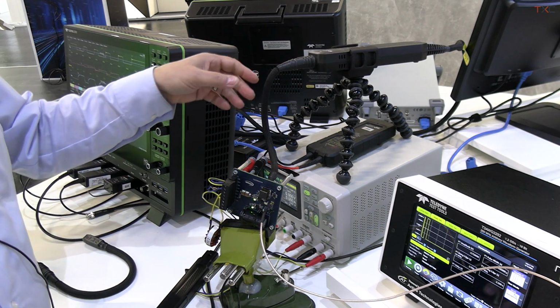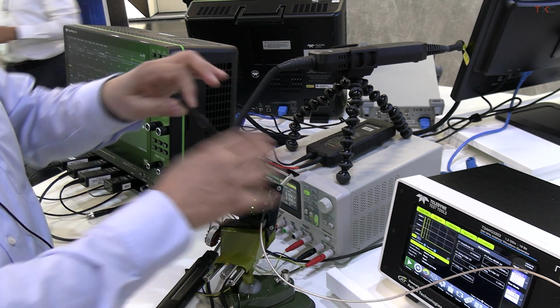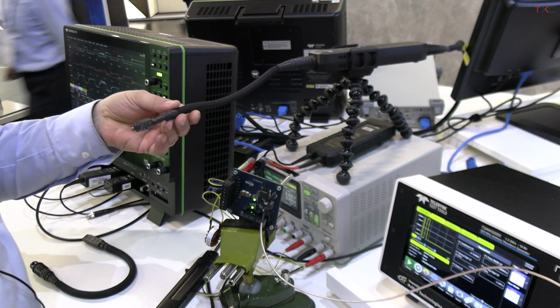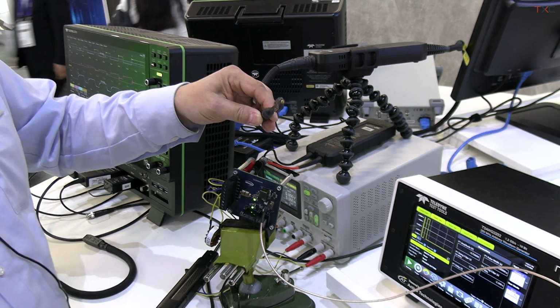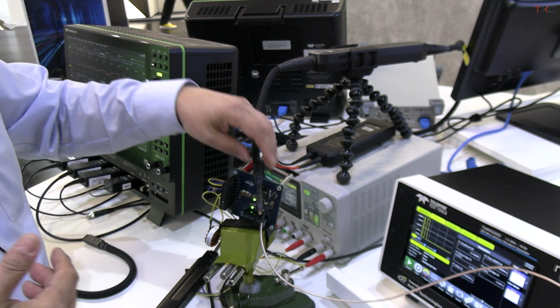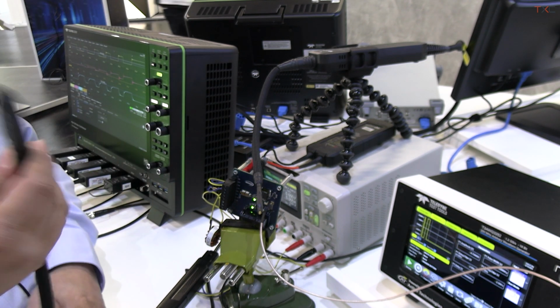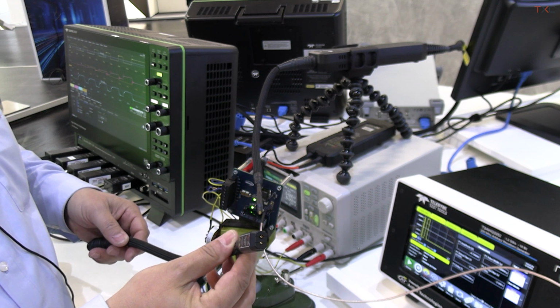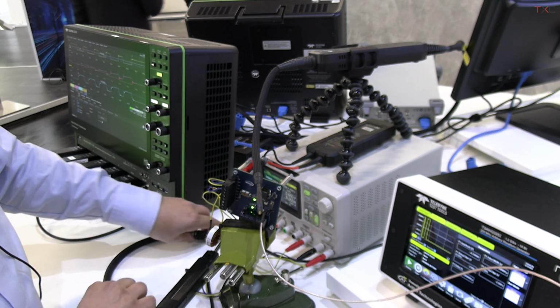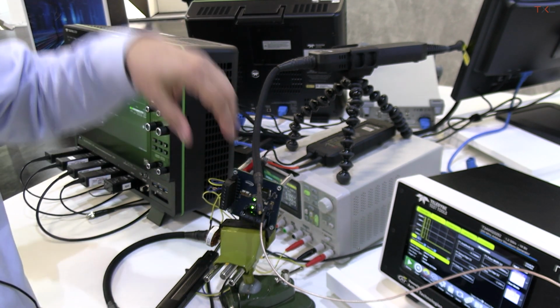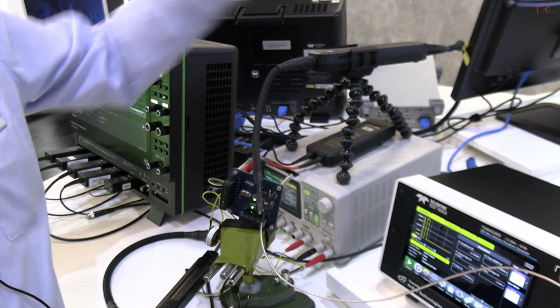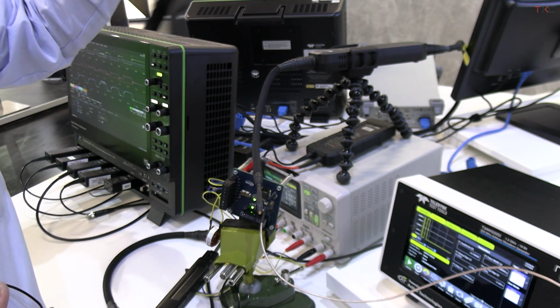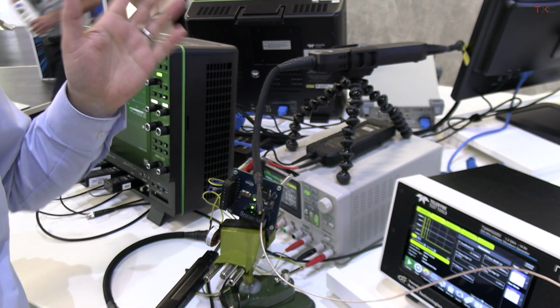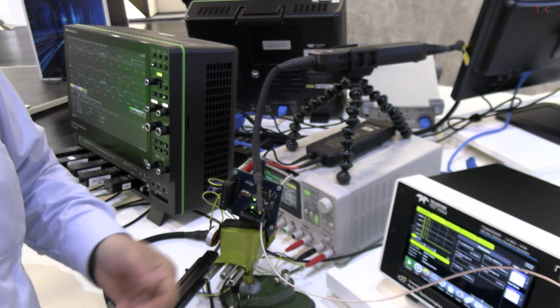Then we have the DL-ISO probe. For the DL-ISO probe, we have different probe tips depending on the input voltage range you want to measure. This tip goes up to 10 volts, up to 200 volts. We use the MMCX connectors, which are more or less a standard in that area. If you need to measure a higher voltage range, you have these strap-in adapters, 1 kilovolt or 2.5 kilovolts. That's a completely optically isolated probe. That means we have an optically powered amplifier in the probe head, where we modulate the signal on a laser and transmit it via fiber to the scope, and then we are completely isolated and can perfectly make the high side gate measurements.